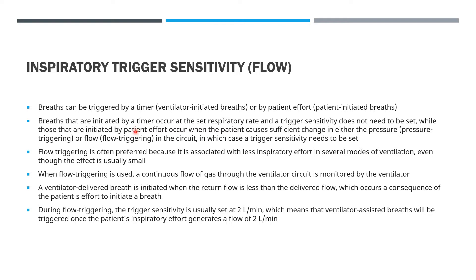Usually, flow triggering is preferred because it is associated with less inspiratory effort. During flow triggering, a continuous flow of gas occurs through the ventilatory circuit which is monitored by the ventilator. When return flow is less than the delivered flow in the circuit, it means the patient is trying to initiate a breath and the ventilator delivers the breath.